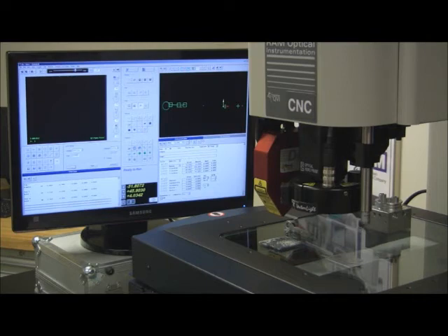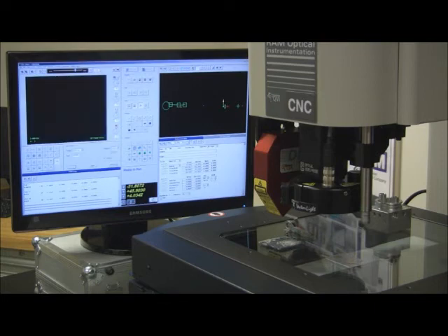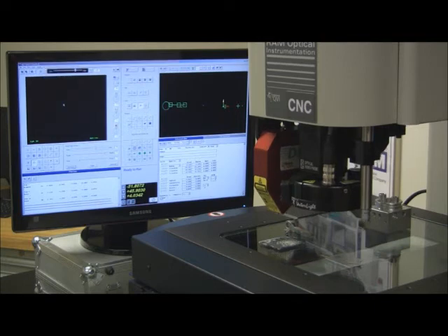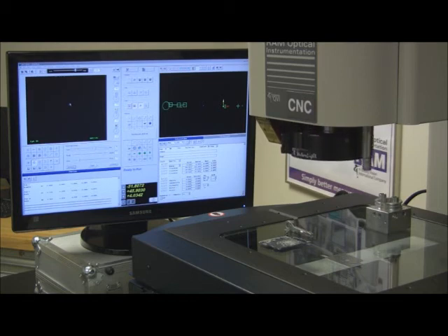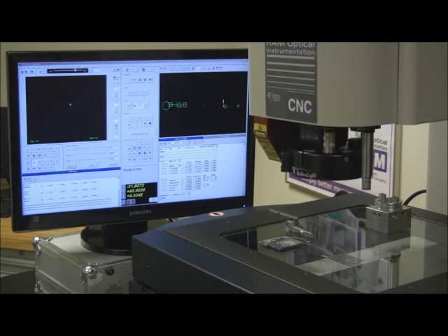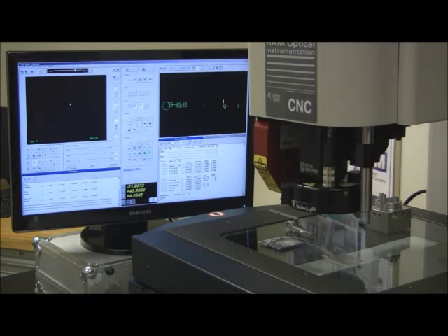And for me to show you the touch probe, what I'm going to do is just select the probe. It'll automatically, I'm sorry, before I do that, I want to retract the laser before I select the probe. And to retract the laser, I'm going to go up to Tools, Change Sensor, Retract Laser. We want to put the laser away so that it's not going to interfere. The laser sits down below the big ring light while it's measuring. I want to get it out of the field of view so that I don't take a chance on encountering any of the other parts as we're going through.